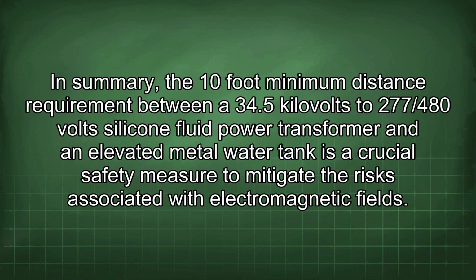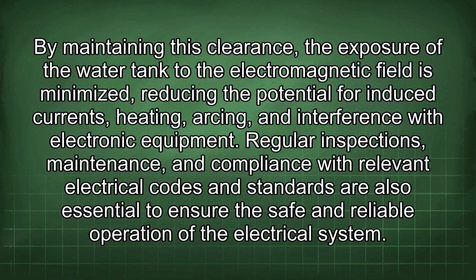are met. In summary, the 10-foot minimum distance requirement between a 34.5 kV to 277/480 volt silicone fluid power transformer and an elevated metal water tank is a crucial safety measure to mitigate the risks associated with electromagnetic fields. By maintaining this clearance, the exposure of the water tank to the electromagnetic field is minimized, reducing the potential for induced currents, heating, arcing, and interference with electronic equipment. Regular inspections, maintenance, and compliance with relevant electrical codes and standards are also essential to ensure the safe and reliable operation of the electrical system.